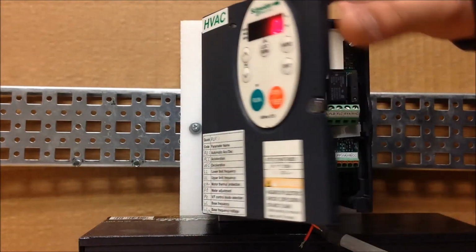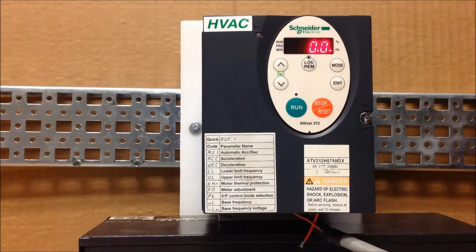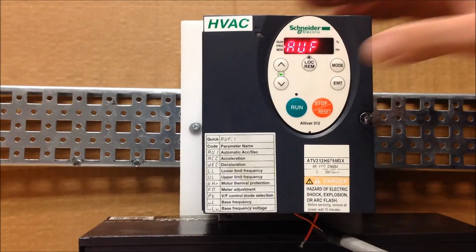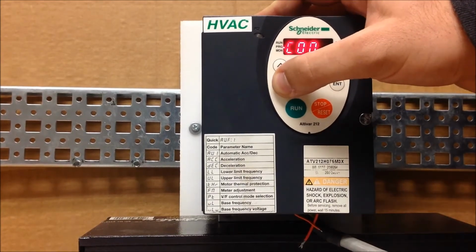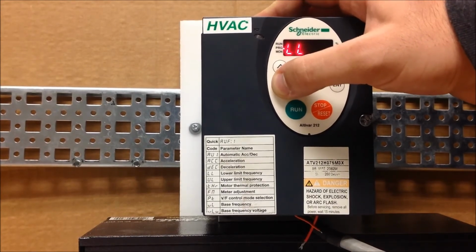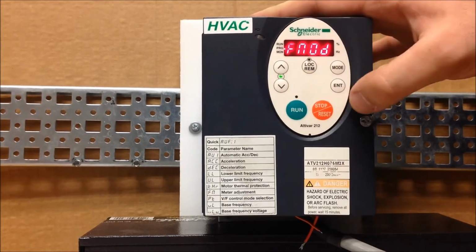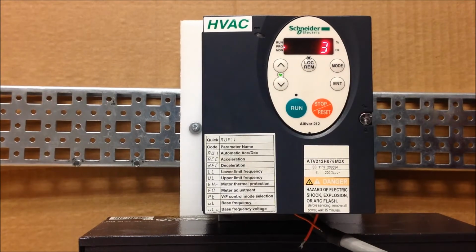So to go into the menus to program this function, the first thing you want to do is program your first channel, which is the FNOD parameter. To get there, you press mode from your main display, you arrow down into FNOD, and you enter on that. FNOD is your reference frequency for the first channel. Depending on what you want this to be, there are 5 options. 1 is VIA, 2 is VIB source, 3 is the HMI keypad up and down, 4 is serial comms, and 5 is plus and minus speed. So let's assume we want to allow your up and down to be your first channel, so you want that to be a number 3.